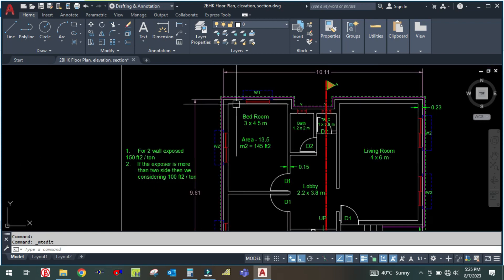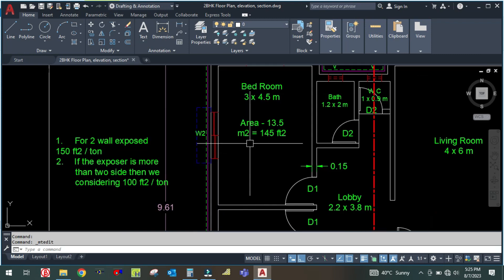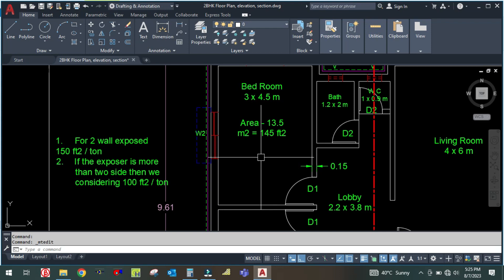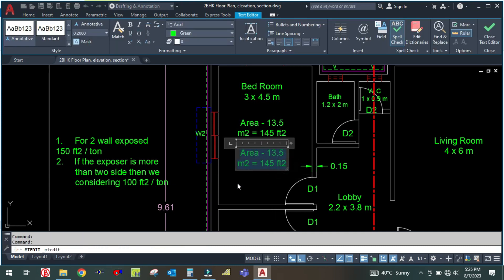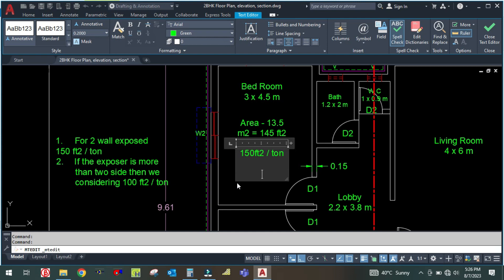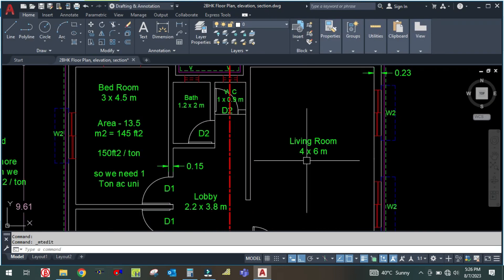The exposed wall is two walls, so we are considering 150 square feet per ton. So 145 divided by 150 gives approximately 1.0, meaning we need a 1-ton AC unit for this bedroom.